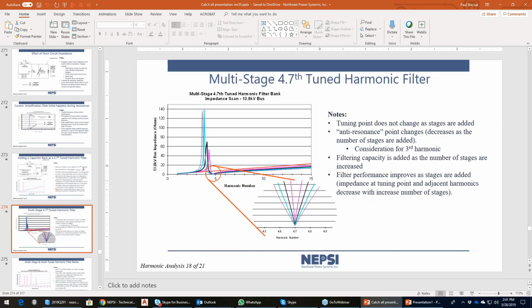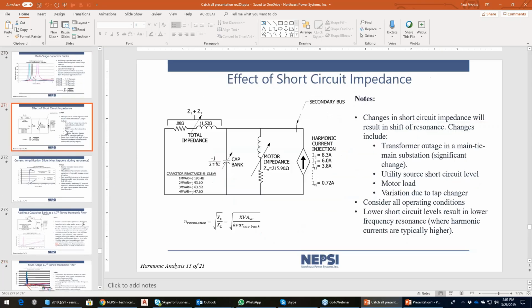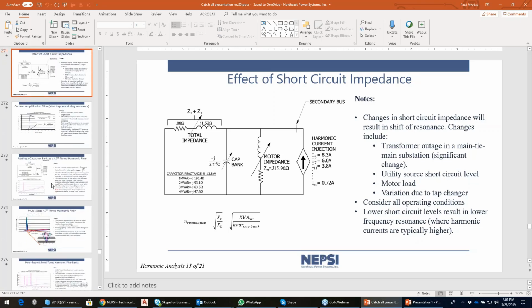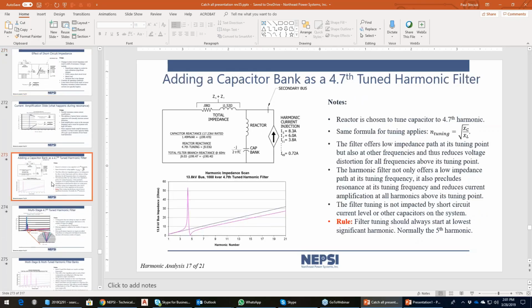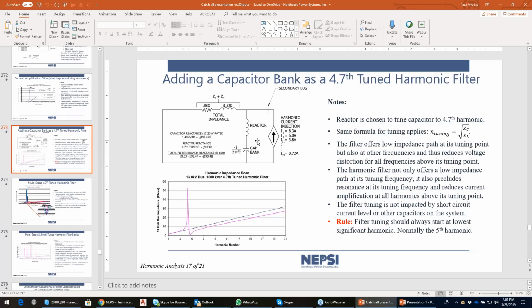A passive filter will bring in harmonic current no matter what value of current you give it. So again, it's an impedance divider here, right? How much current flows into the source versus how much flows into the filter. So if you present it more current, it will take in more current and will burn up. So with passive filtering, you need to be careful to make sure that you have not exceeded its capabilities. It's also a good reason why you should be putting some type of protection on your harmonic filter bank, because if the harmonic load in the plant goes up, it may exceed the initial design rating of the harmonic filter, and you could overheat and burn the filter up.